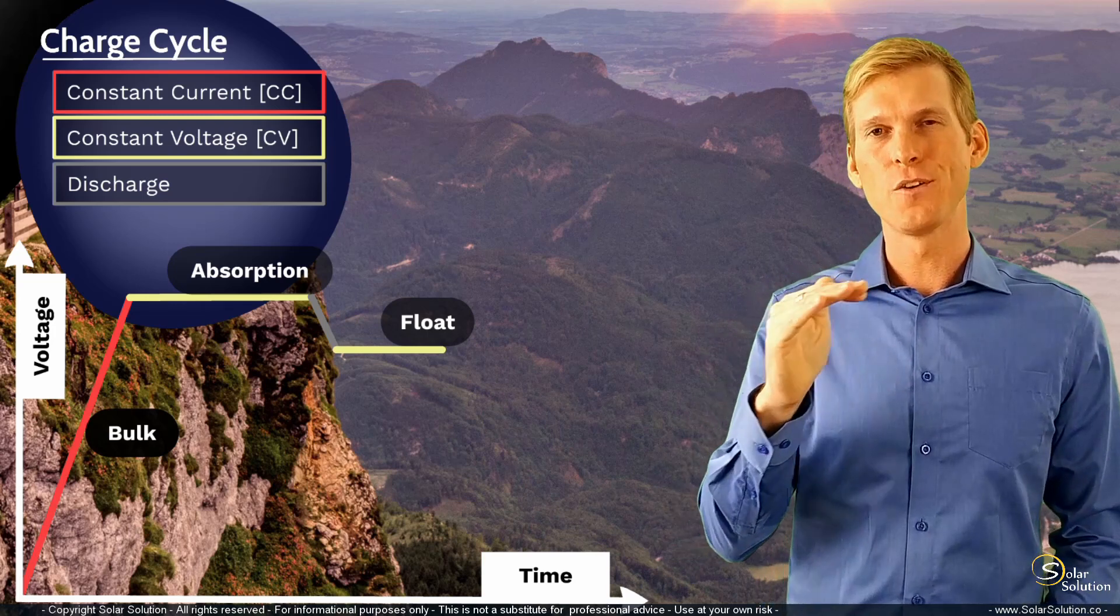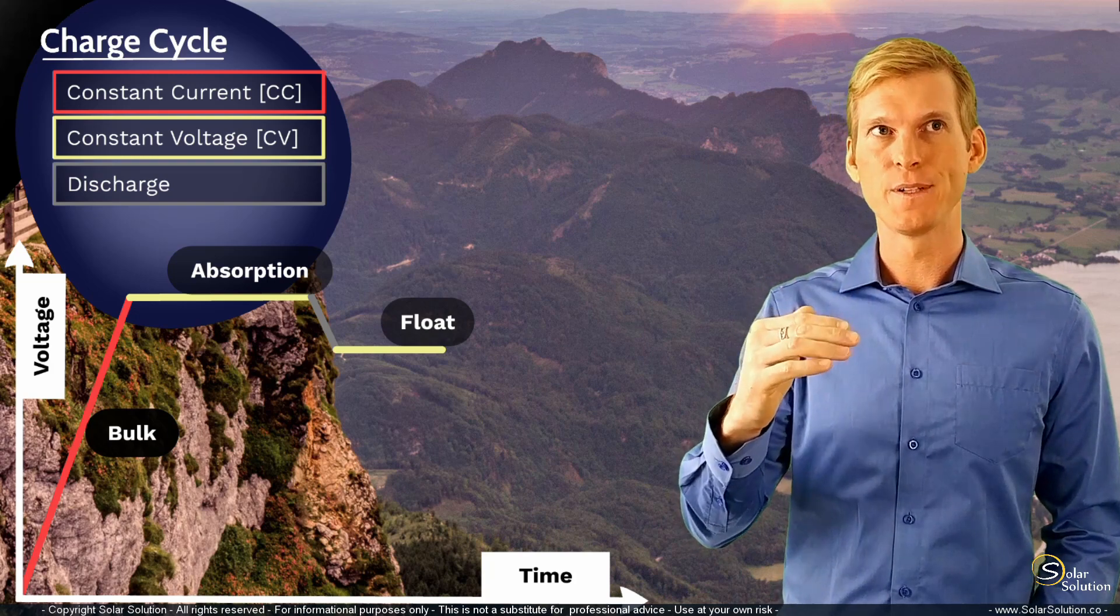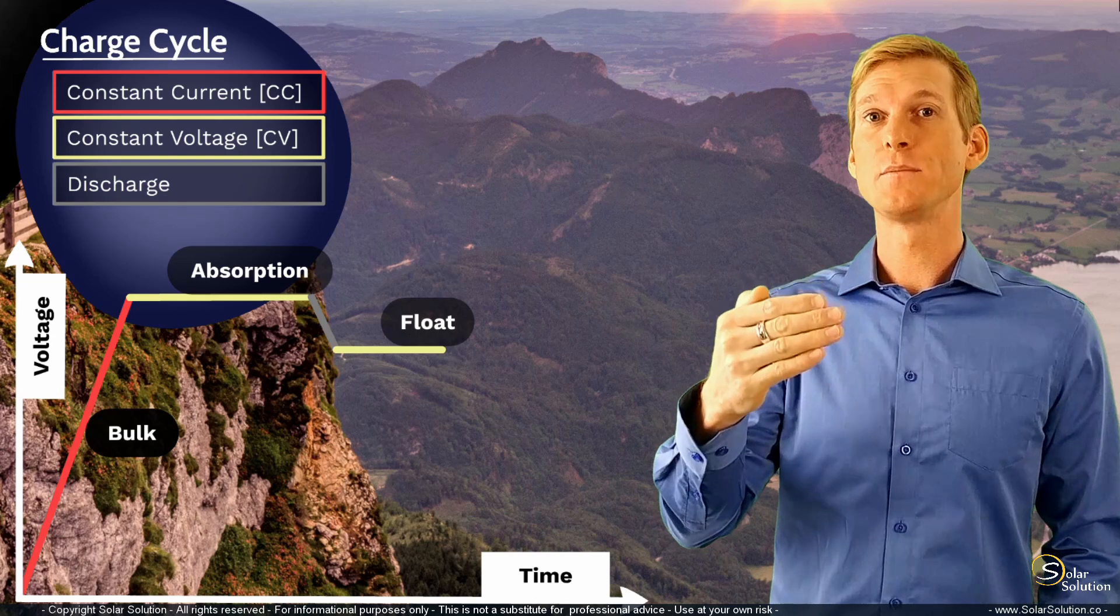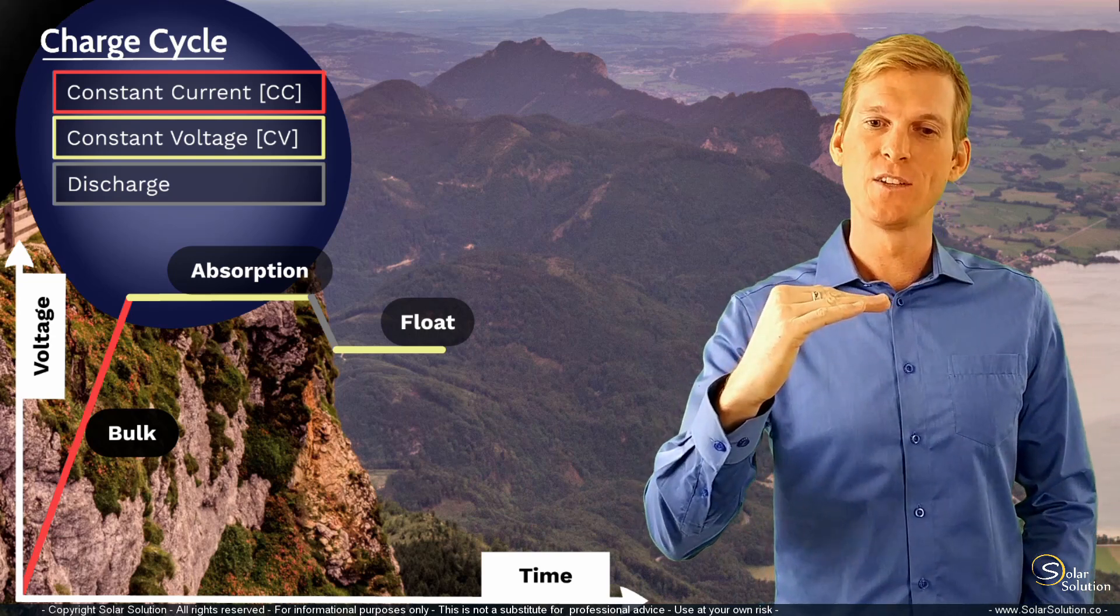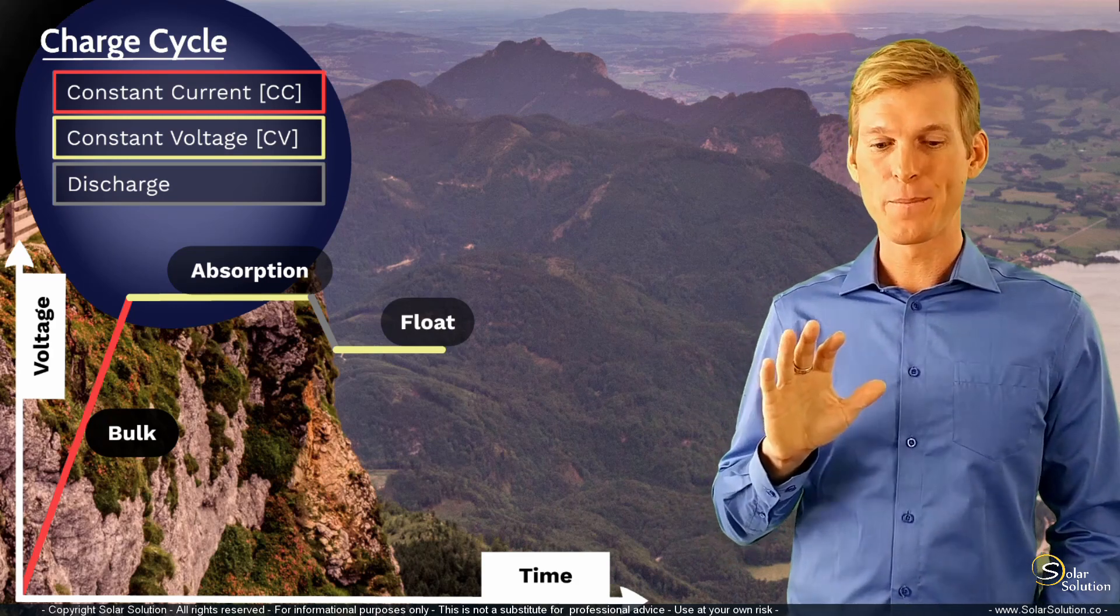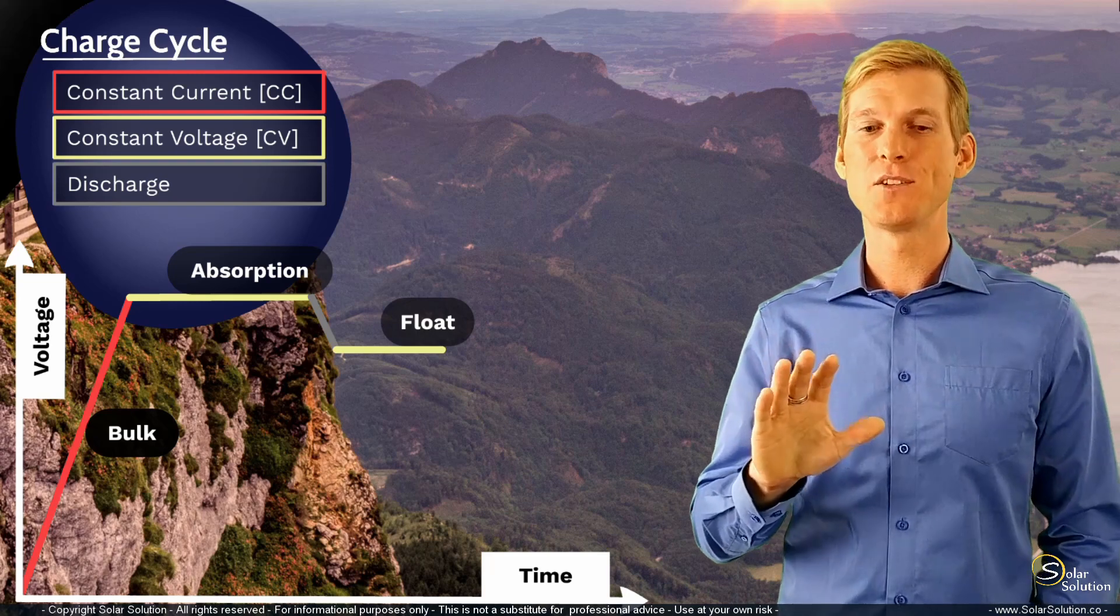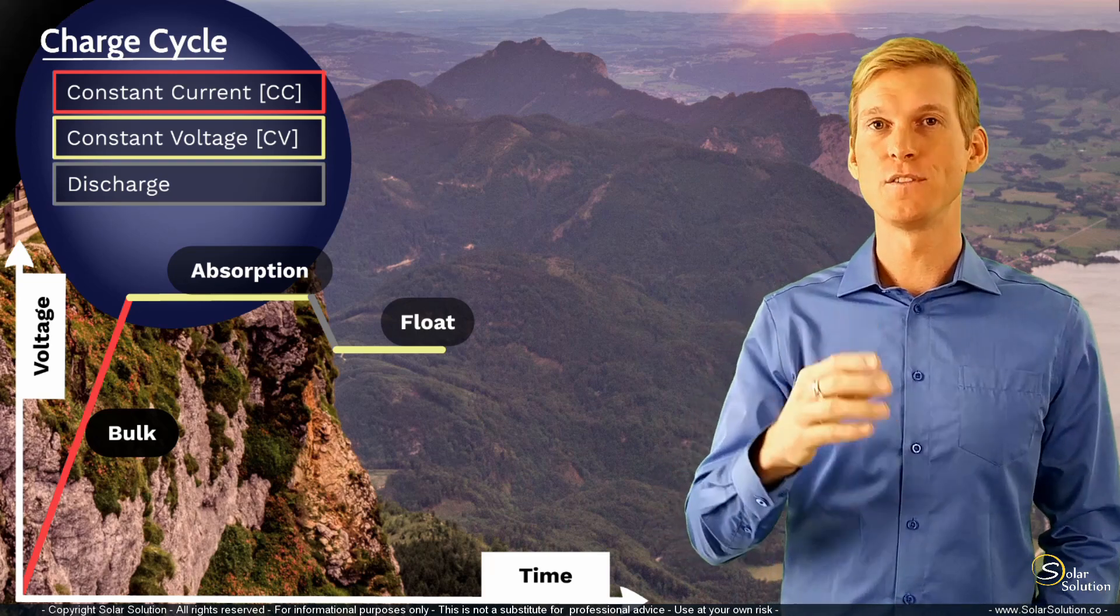And the purpose of the float stage is to make sure that you no longer continue to charge the battery, so it avoids that you're overcharging the battery and therefore damaging the battery, but it also avoids that the battery slowly discharges. Because you're actually still pushing energy into the battery, a small amount, but you're still pushing energy into the battery.